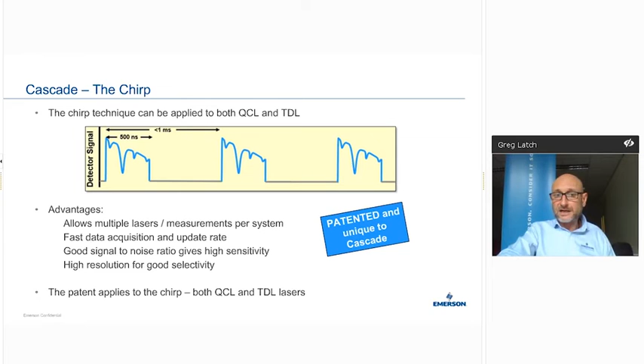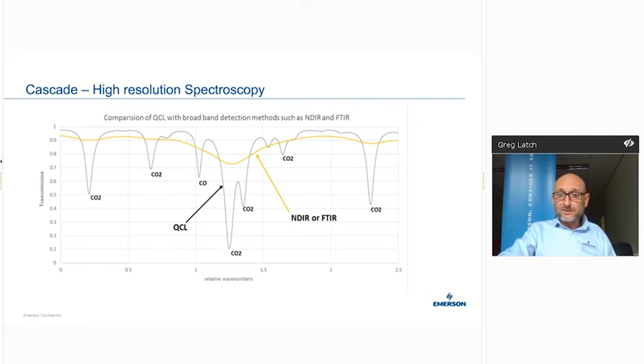for our cascade analysis. Again, compared to traditional technologies, this gives you a snapshot of the clarity and of how we can look at different QCL points or wave numbers and optimize the measurement. We're physically looking for a component of interest, so depending on the wave number, we optimize the measurement to get what we call the best fit, which we'll talk about on the next slide, so there's no overlay or potential noise from any other components of interest, compared to traditional technologies like IR, for example, in the non-dispersive, etc. Okay, spectral fittings.